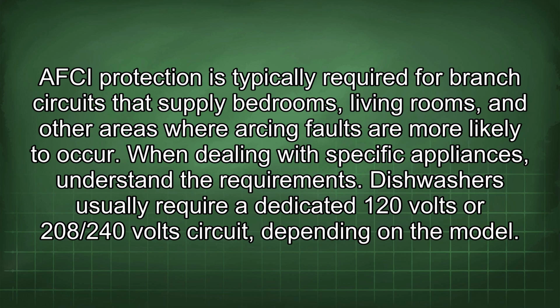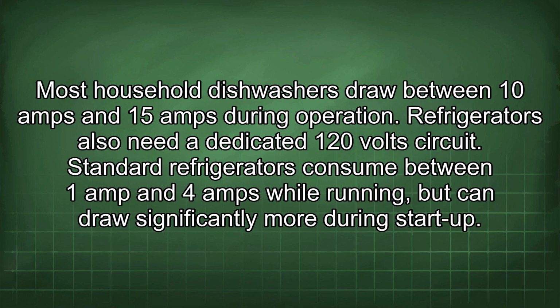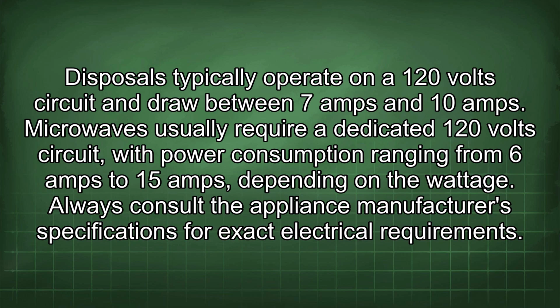Dishwashers usually require a dedicated 120 volt or 208/240 volt circuit depending on the model. Most household dishwashers draw between 10 amps and 15 amps during operation. Refrigerators also need a dedicated 120 volt circuit. Standard refrigerators consume between 1 amp and 4 amps while running, but can draw significantly more during startup. Disposals typically operate on a 120 volt circuit and draw between 7 amps and 10 amps. Microwaves usually require a dedicated 120 volt circuit, with power consumption ranging from 6 amps to 15 amps, depending on the wattage. Always consult the appliance manufacturer's specifications for exact electrical requirements.